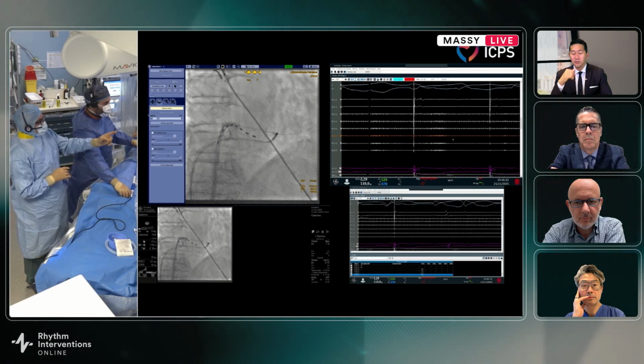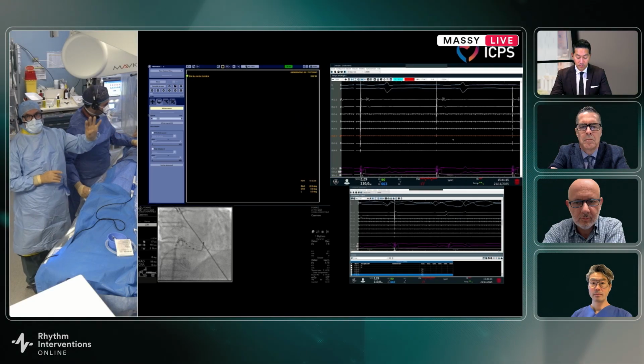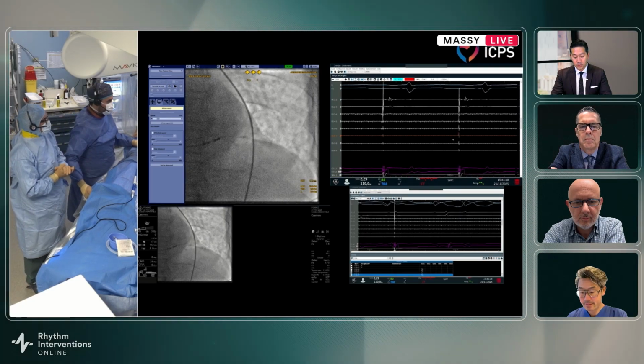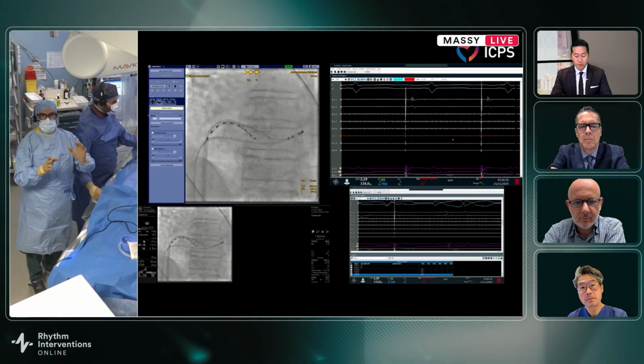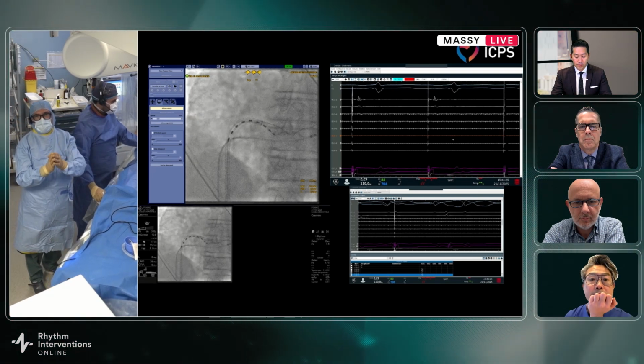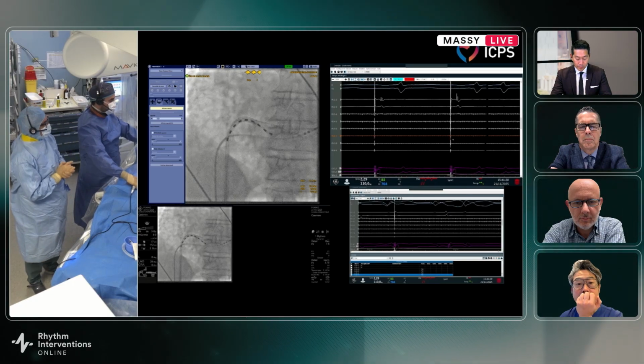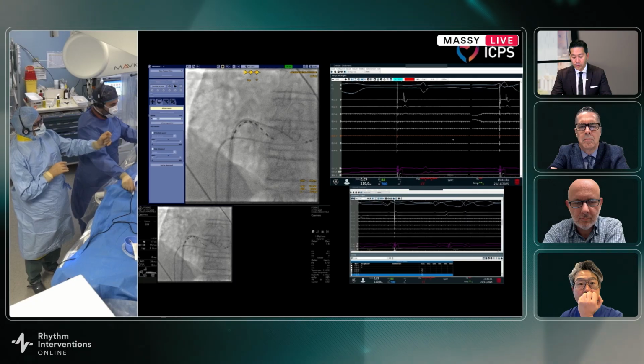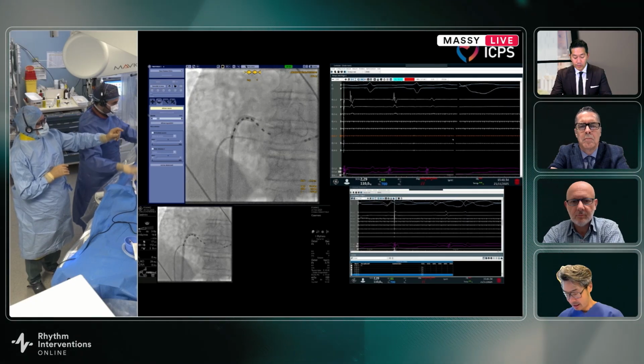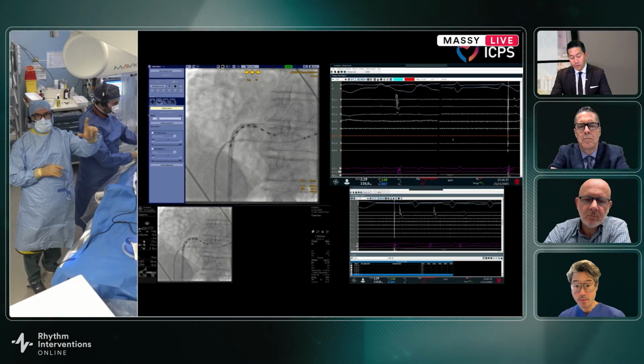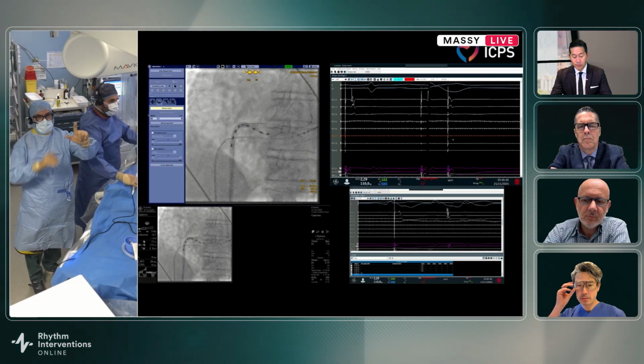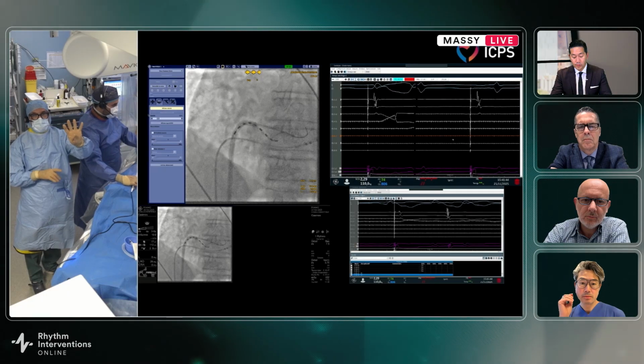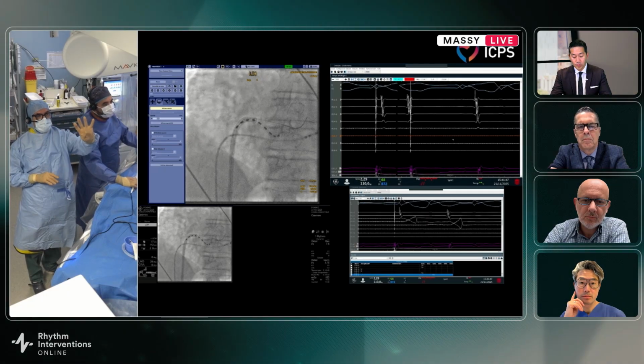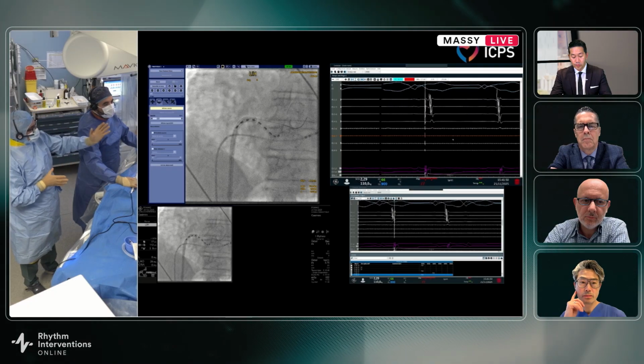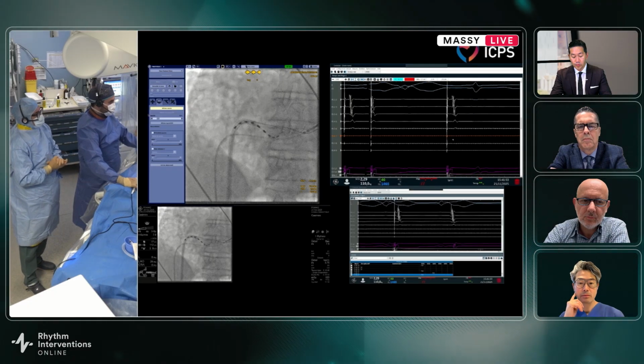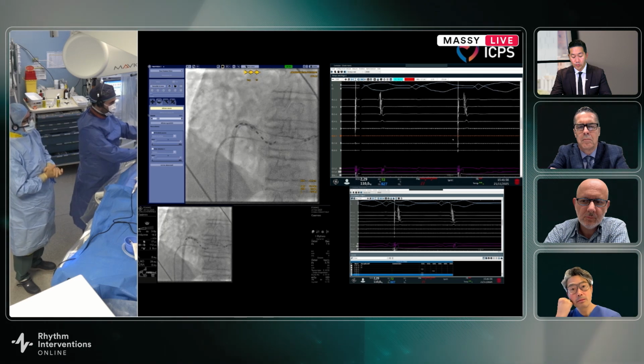Salem is now pushing out the first four electrodes. Let's say 4 electrodes will mimic or correspond with an 8 or 10 millimeter tip RF electrode. PF will be delivered between 1, 2, 3, 4. So if you push out only 3, it delivers PF only between 1 and 2. So the balance we've decided to choose is to push out 4 electrodes. So we have now something like a 15 or 20 millimeter RF catheter.